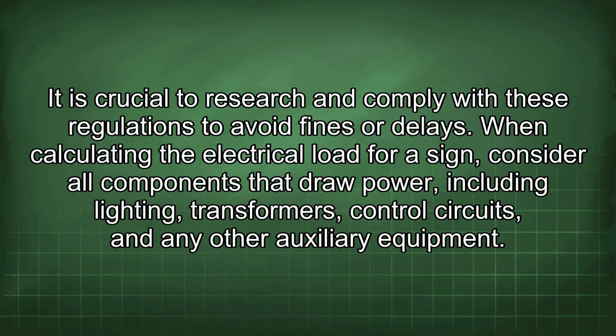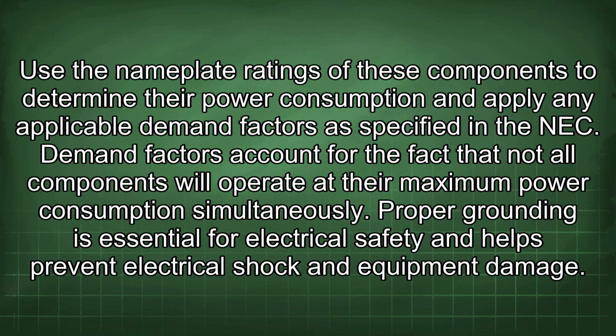When calculating the electrical load for a sign, consider all components that draw power, including lighting, transformers, control circuits, and any other auxiliary equipment. Use the nameplate ratings of these components to determine their power consumption and apply any applicable demand factors as specified in the NEC.